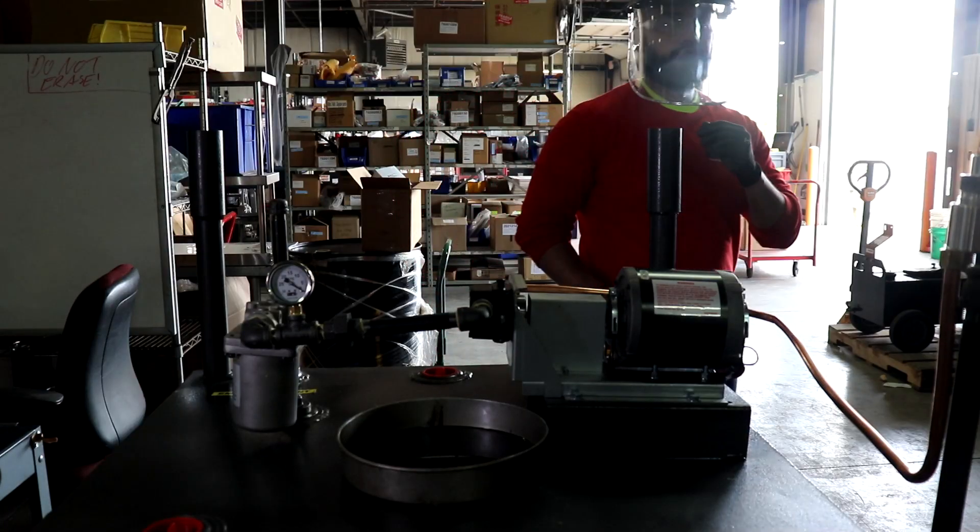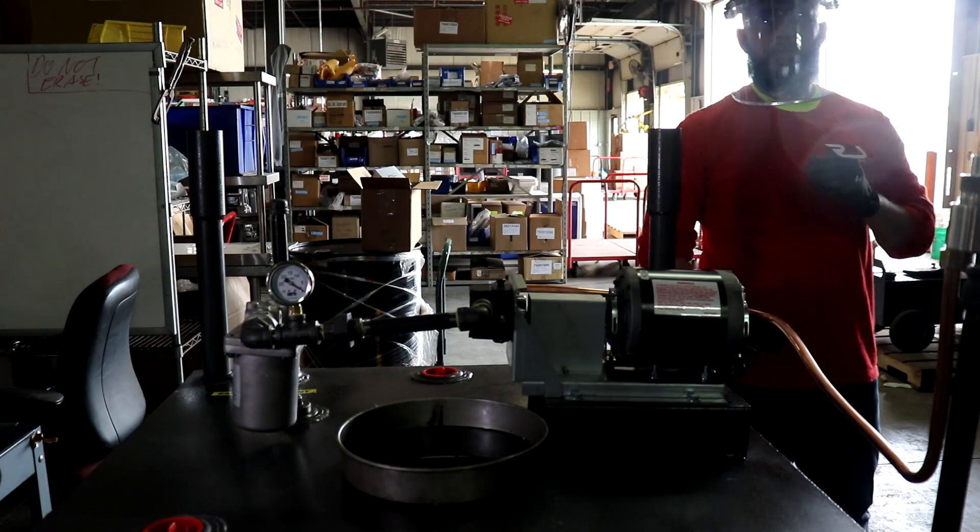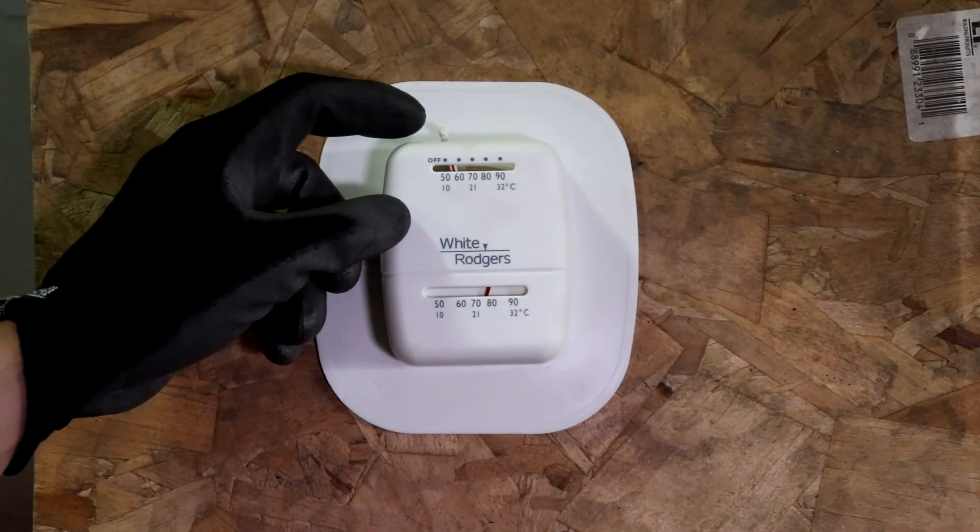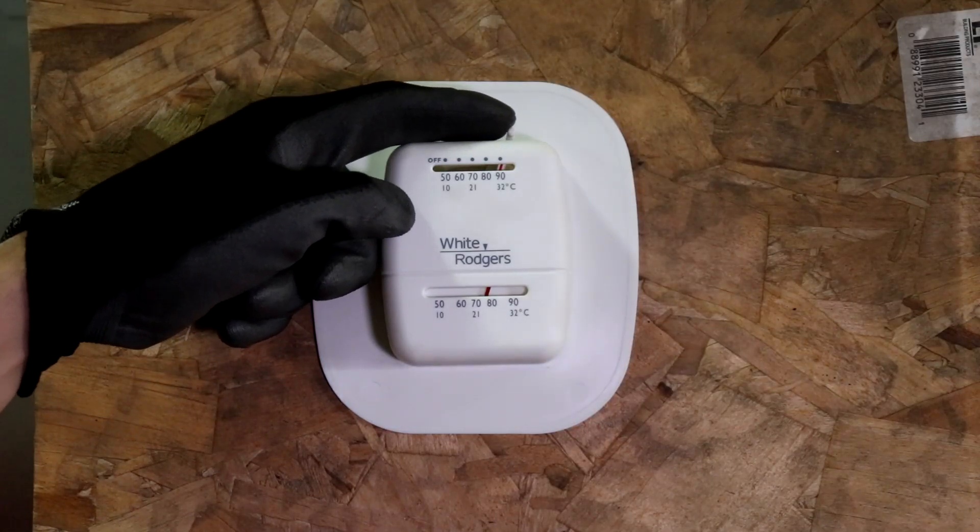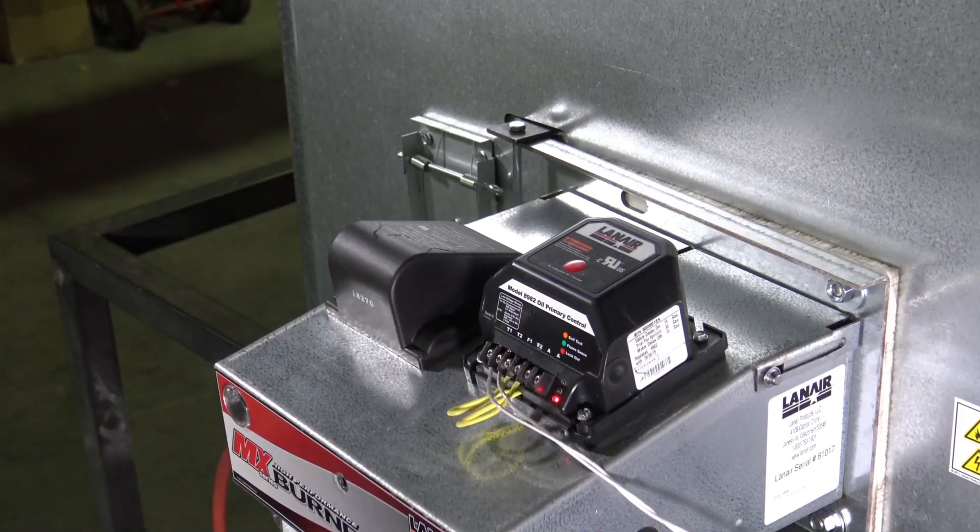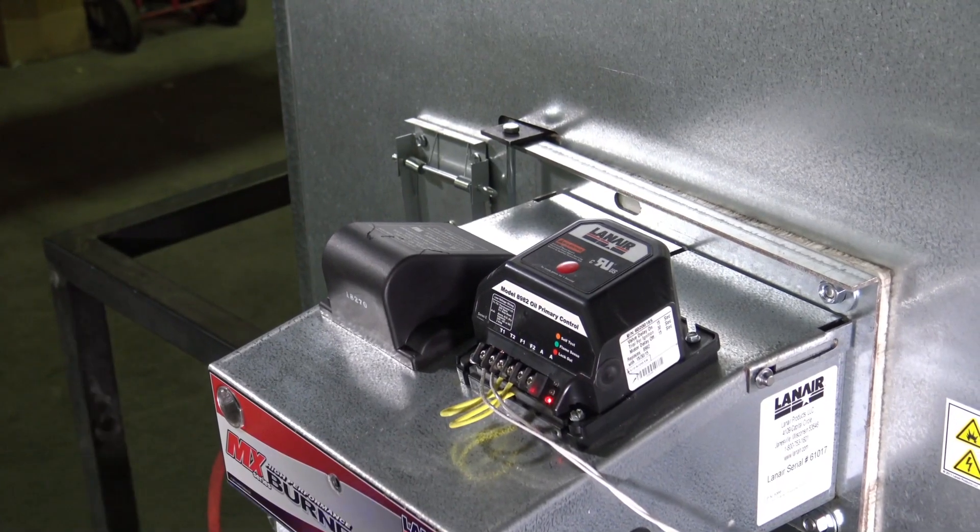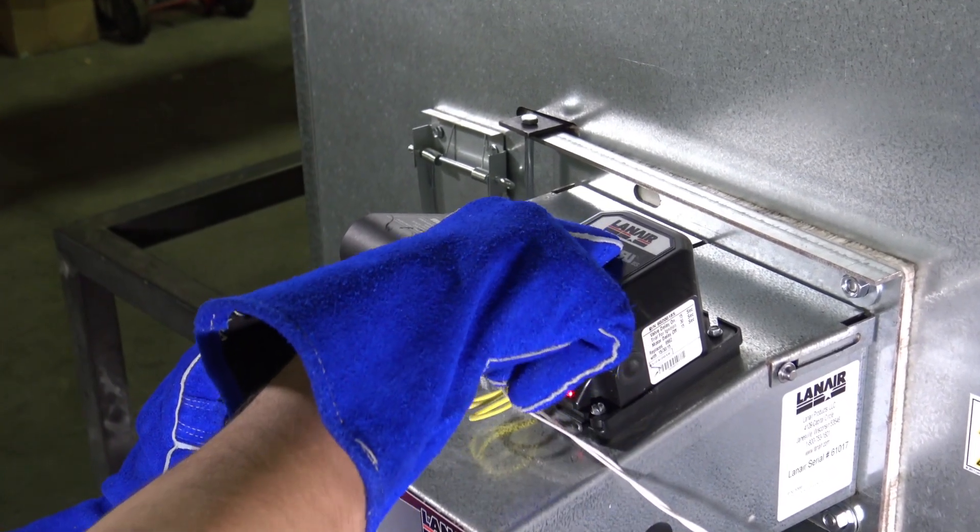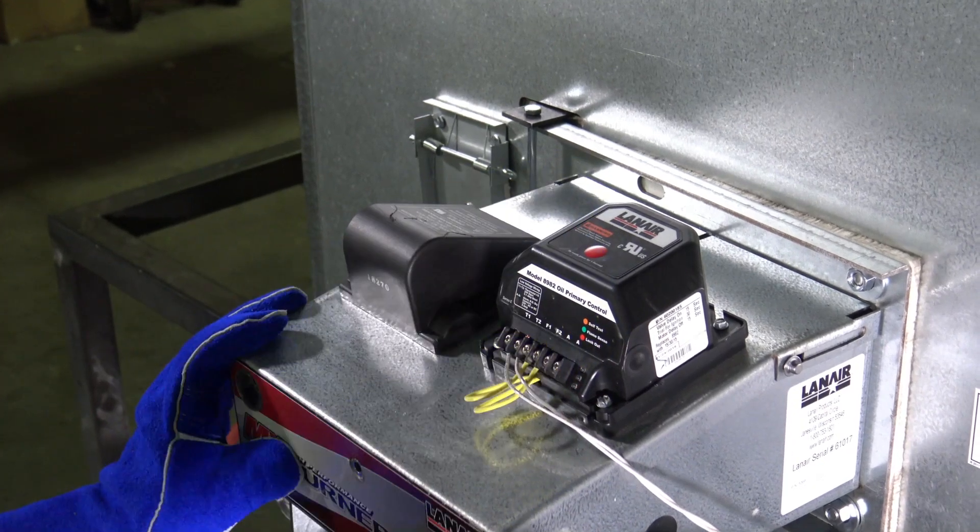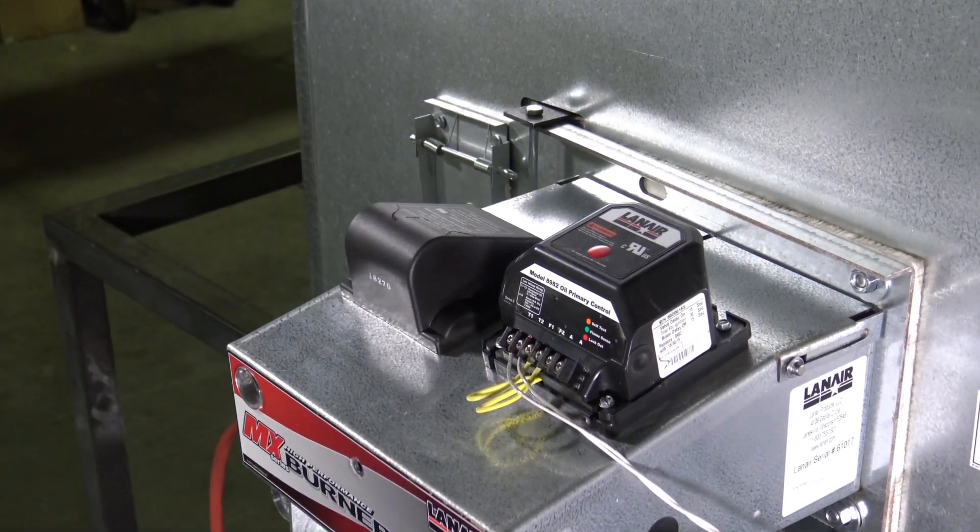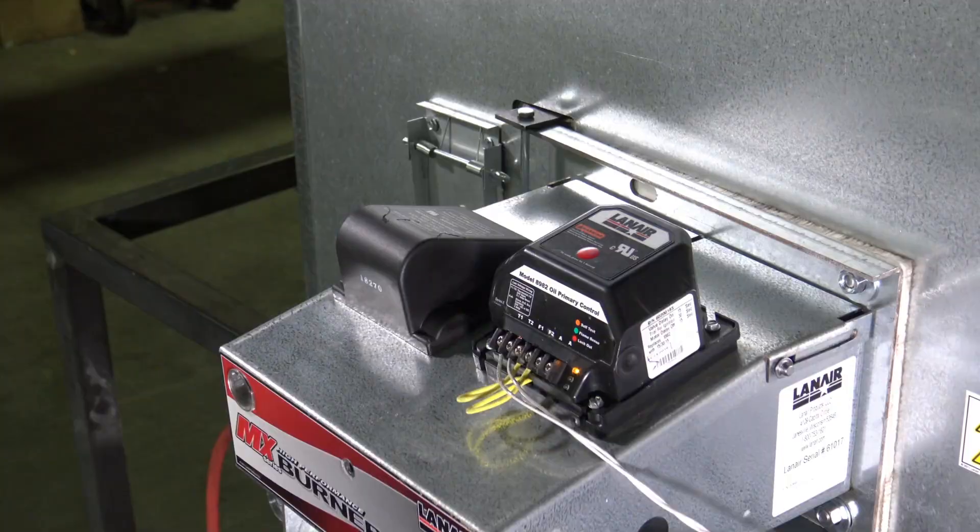Once proper fuel quality and storage can be confirmed, continue with the flame adjustment. Establish a call for heat to the unit by setting the thermostat to its maximum temperature setting. If the red light on the burner's primary control is indicating that the unit is locked out, you will need to press the reset button on the top of the primary control to reset the burner. The unit should now attempt to start operating. Allow the heater to run for at least 15 minutes to reach its operating temperature before proceeding.